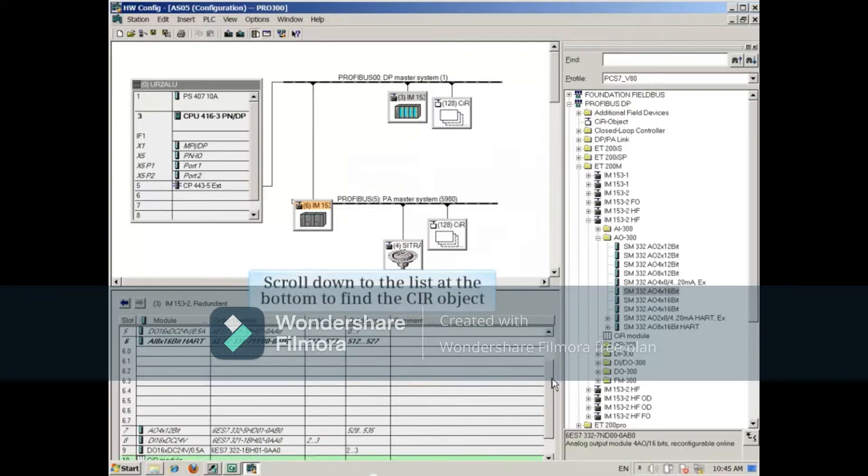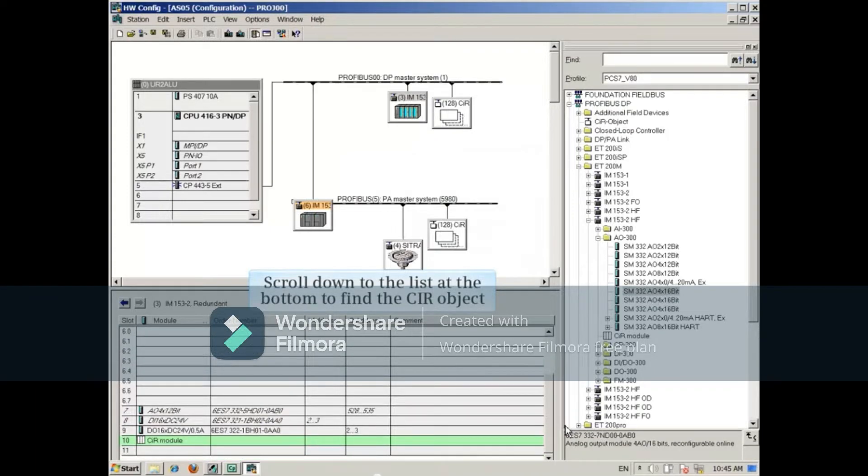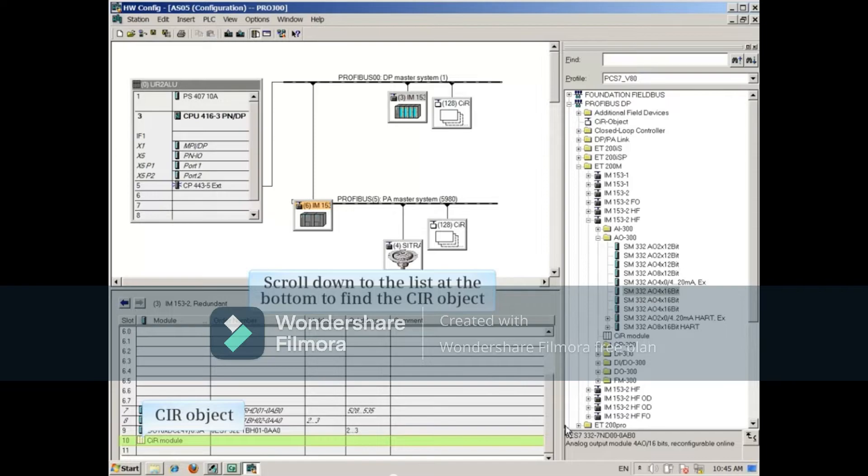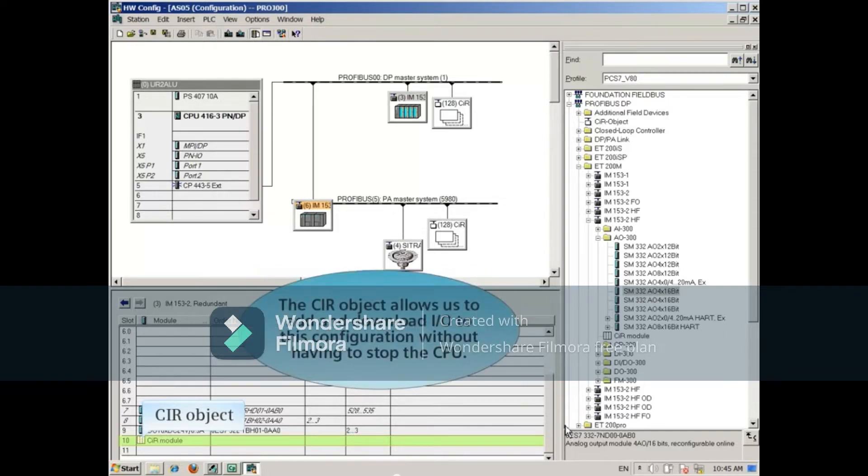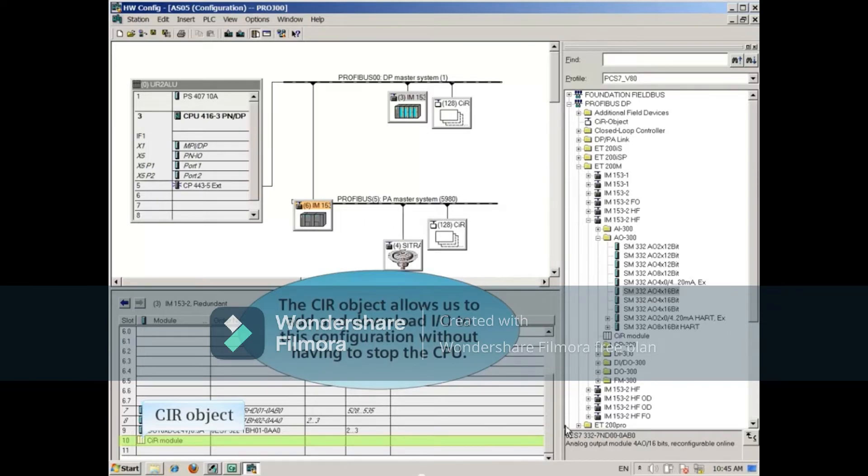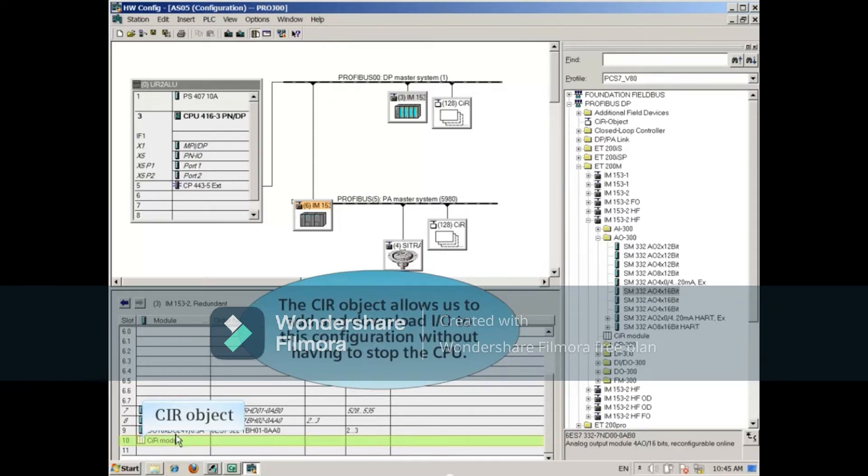Scroll down to the list at the bottom to show the CIR object. The CIR object allows us to add and download IO to this configuration without having to stop the CPU. If you're not using CIR, this object will not be here.